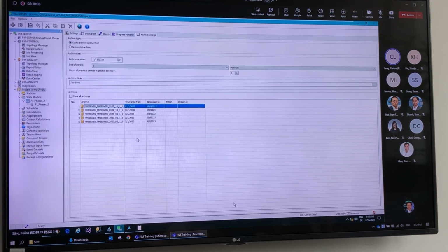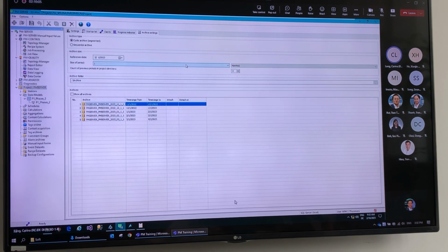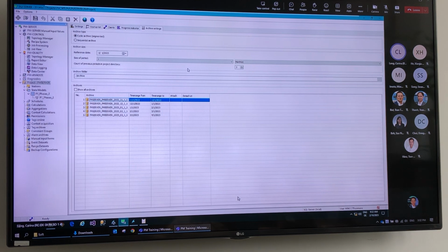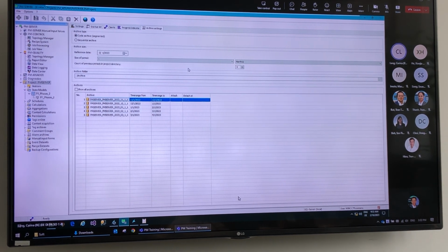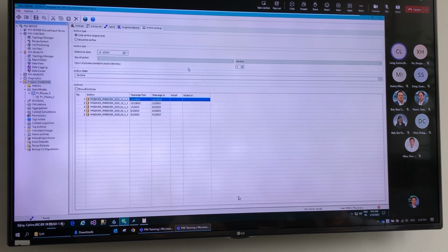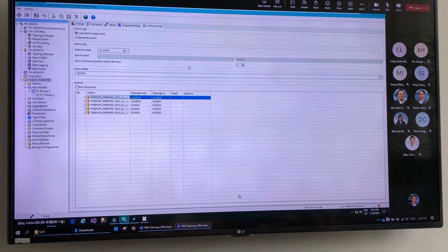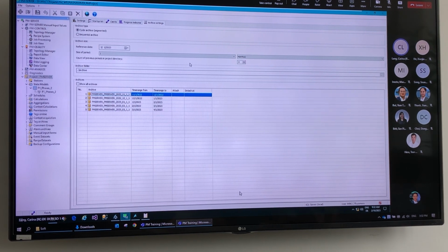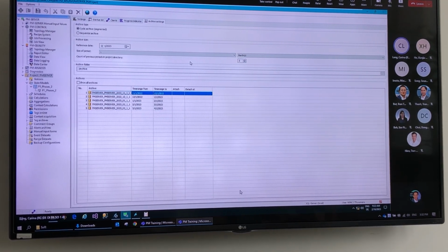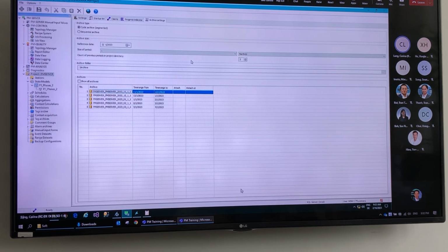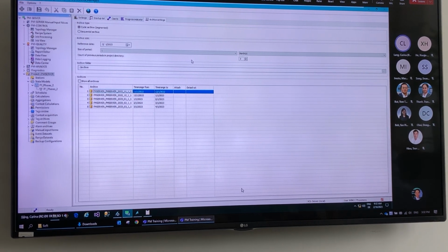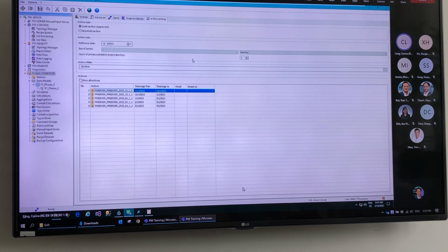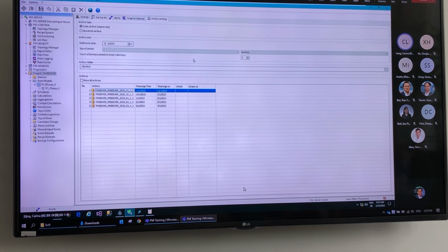So it means we need to change the size of period or even the count of previous periods so that we have an archive available for the time range we want to insert the historical data. So just for information, when I started working with the PM server and the PM analyze part, and I wanted to import historical data, I was wondering why I do not receive the data and why I do not get access to it. And then I had to find out what the problem was, and it was exactly this scenario.